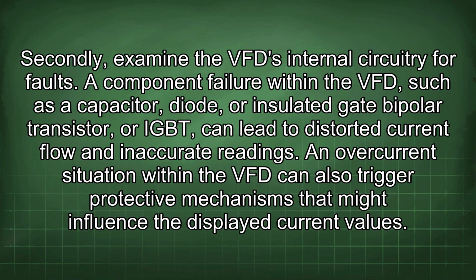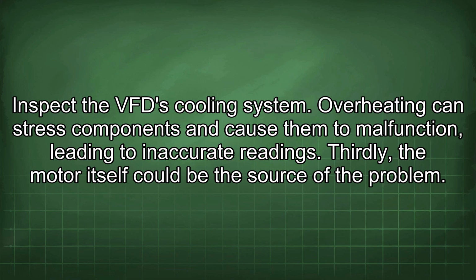Secondly, examine the VFD internal circuitry for faults. A component failure within the VFD, such as a capacitor, diode, or insulated gate bipolar transistor, can lead to distorted current flow and inaccurate readings. An overcurrent situation within the VFD can also trigger protective mechanisms that might influence the displayed current values. Inspect the VFD cooling system. Overheating can stress components and cause them to malfunction, leading to inaccurate readings.